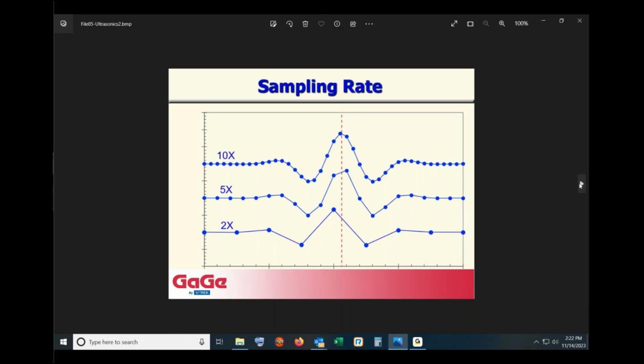You can see that by sampling faster, really the sampling interval, the width between the samples, determines how accurately you can measure the position of that echo, which is usually paramount in ultrasonic measurements. You can see in the bottom one, we're kind of lucky that the peak actually falls fairly close to that vertical dashed line, but it might have fallen as far away as a full sample away. And then on the top one, we get a much better view. So the sampling rate, or more precisely, the sampling interval, sets the scale of how accurately you can determine the position in time of an ultrasonic echo. So the feature of high sampling rate translates directly into the benefit of good echo localization in time.